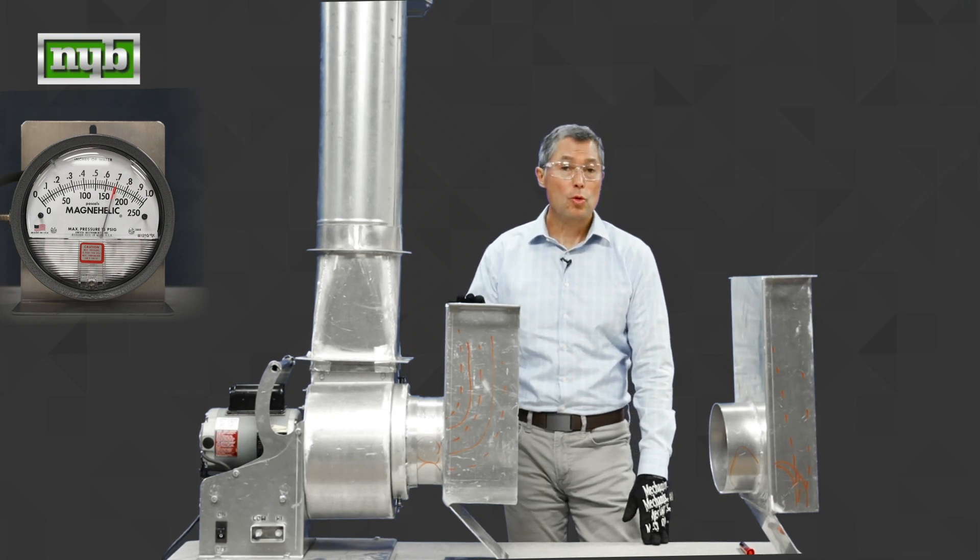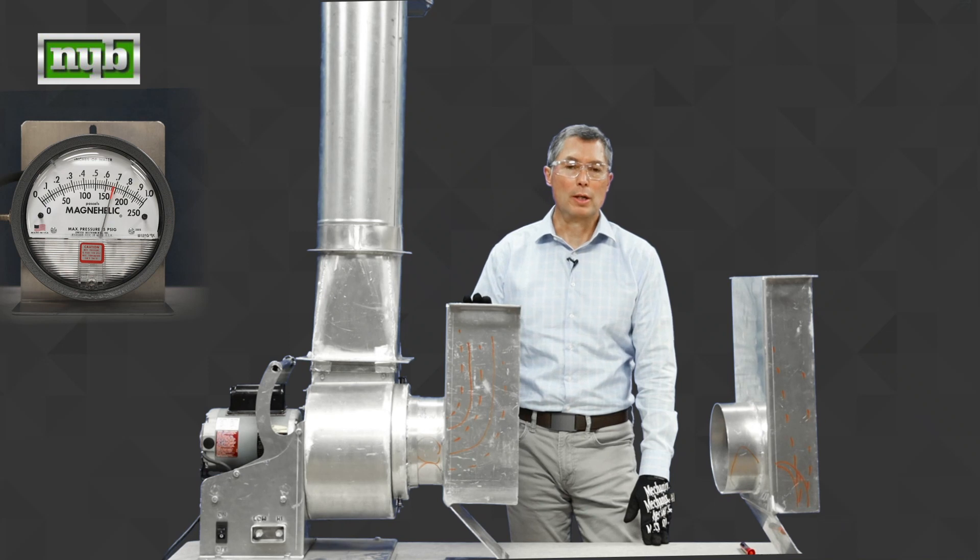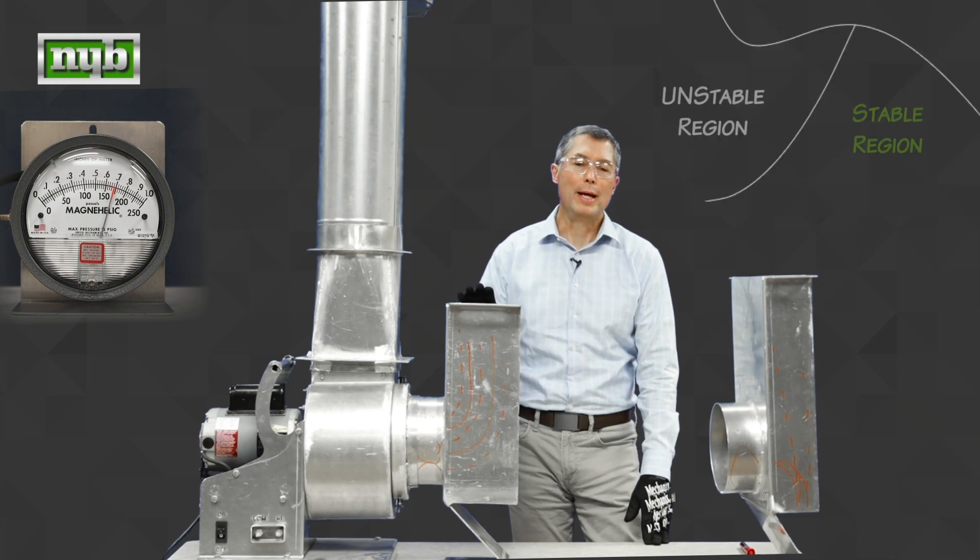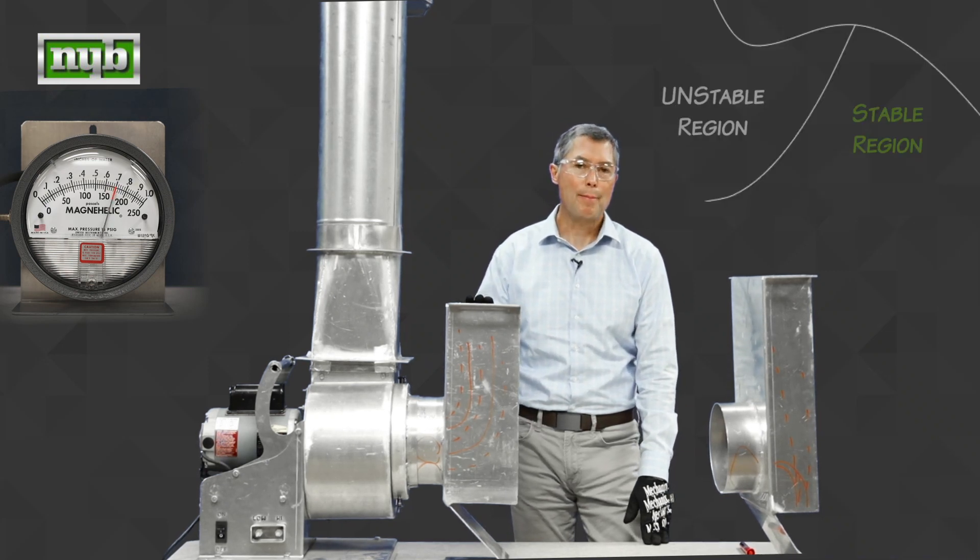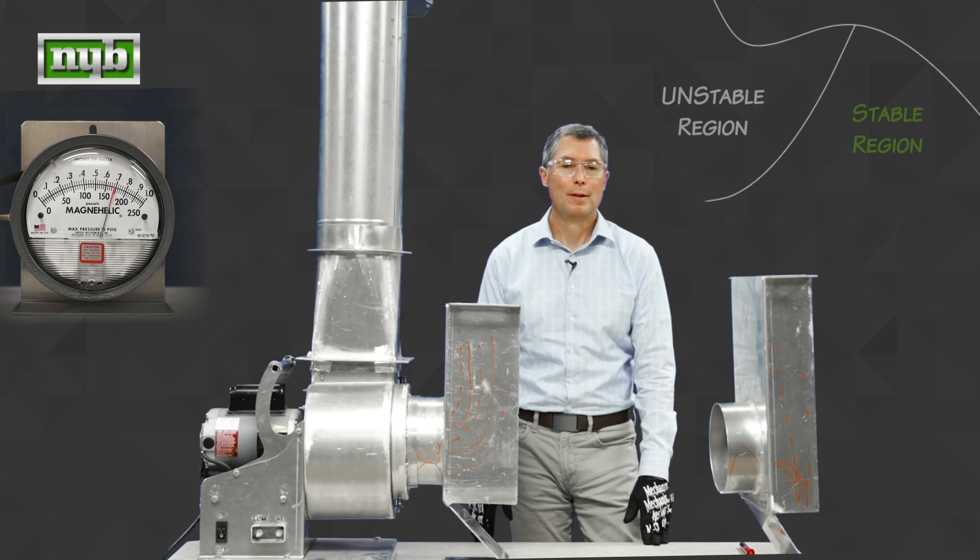And finally, notice the tone of the fan is not droning any longer. It's at a steady state as well. And that's because we're now at a stable operating point on the fan curve. Let's move on to final thoughts.